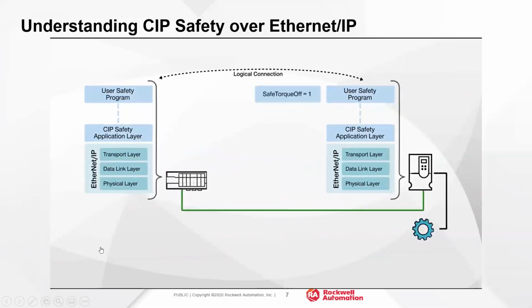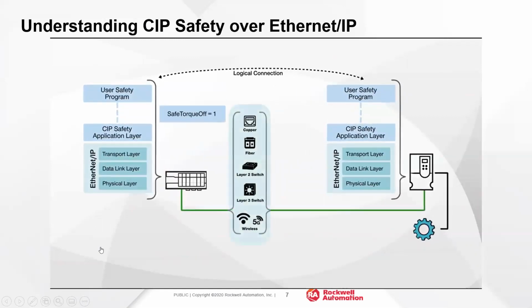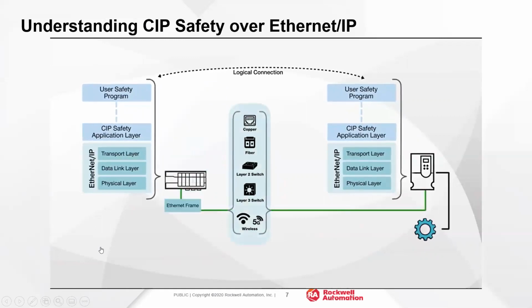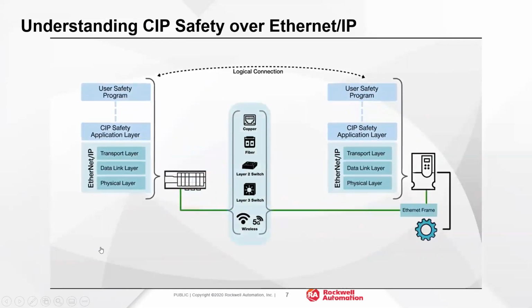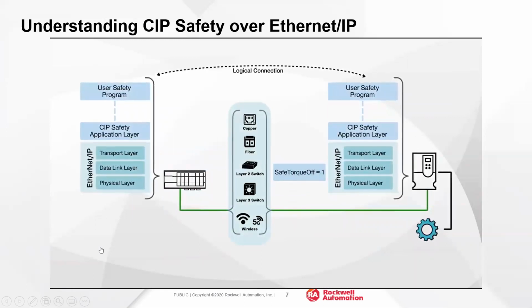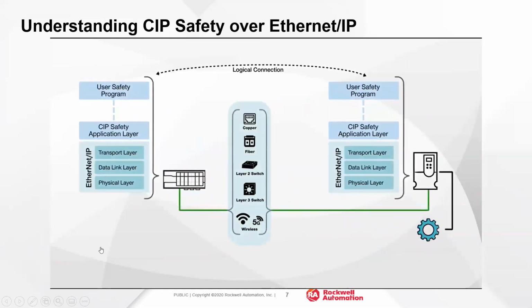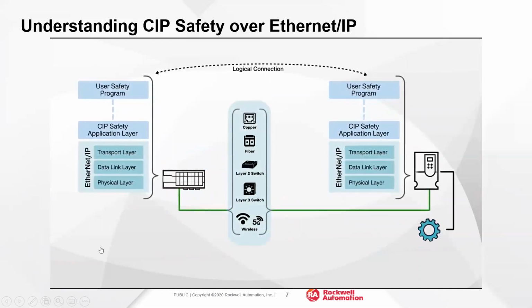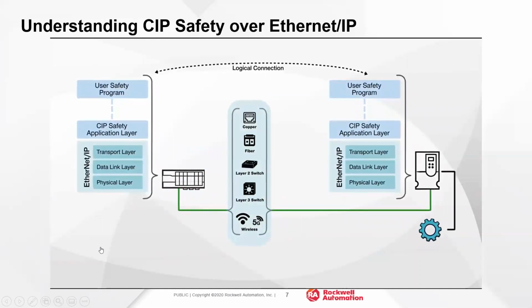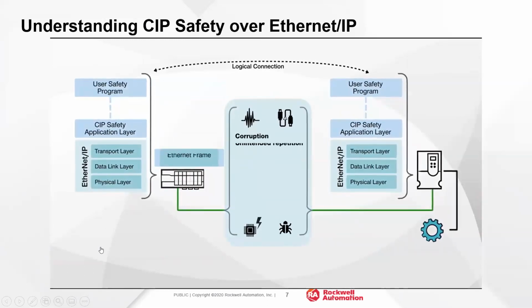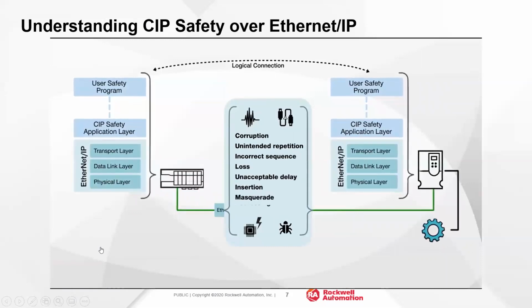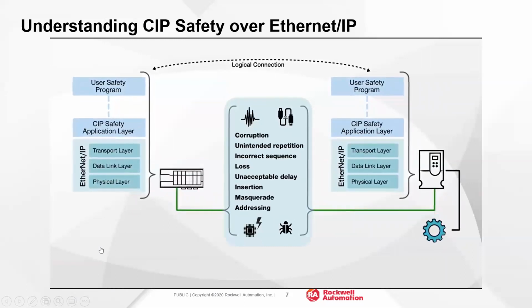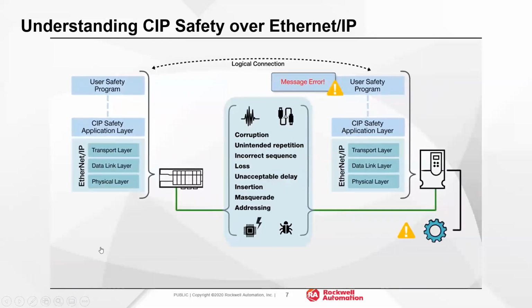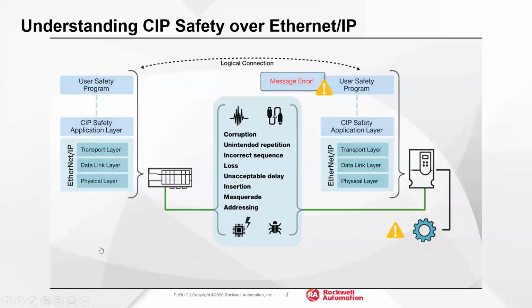Since making a safety-rated network would be impractical, the CIP Safety protocol leverages the black channel principle, putting the intelligence in the end devices instead of the network hardware. That means maximum flexibility of network design is possible without compromising safety. The end devices perform the diagnostics on the CIP Safety protocol to detect each type of error that could occur in the network, so that the device can still go to a safe state when an error occurs. Let's look at how those errors are mitigated.